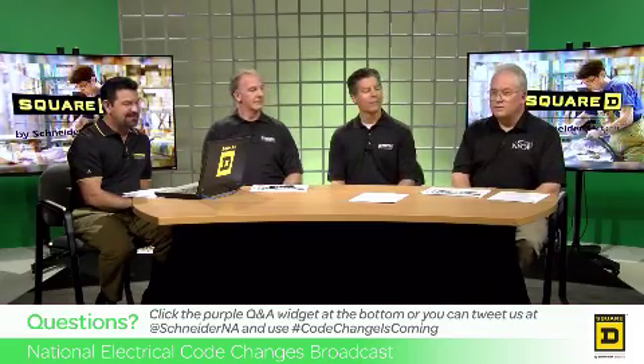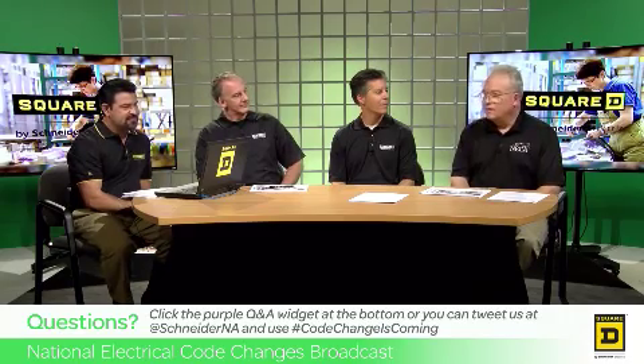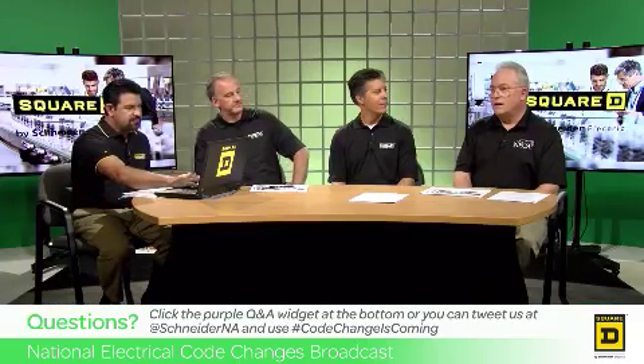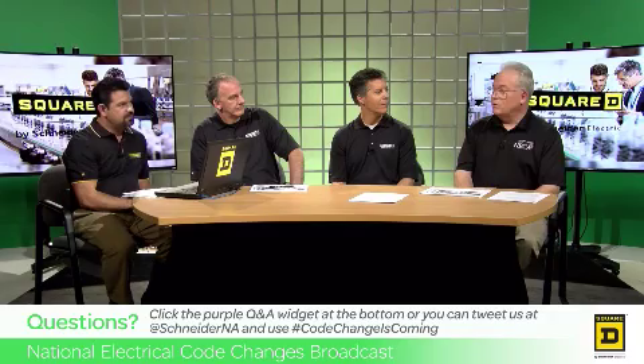Let's see the next one. Why are the receptacle outlets required within 6 feet of the wall in rooms wider than 12 feet? Shouldn't it be no less than 6 feet? Otherwise, I could put one 6 inches from the wall, and that provides no advantage over a wall outlet. That's a good question, Phil. I covered that change, so I'll respond. The 6 foot measurement comes primarily from the standard length of a cord supplied with equipment. The cord is typically, by the product standard, a length of 6 feet. And if you get further away from the wall than 6 feet, you start looking for use of extension cords if there's no receptacle available. So that's really what's driving that 6 foot measurement from the wall, in addition to the receptacles that would be required for the wall space in that section.